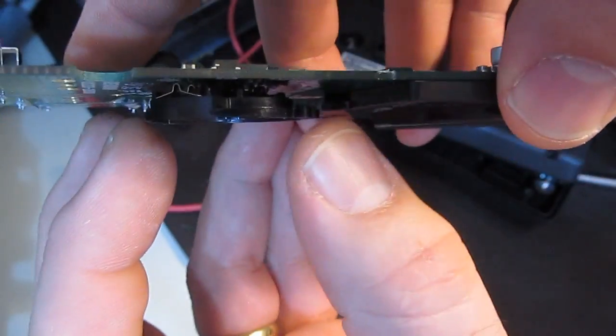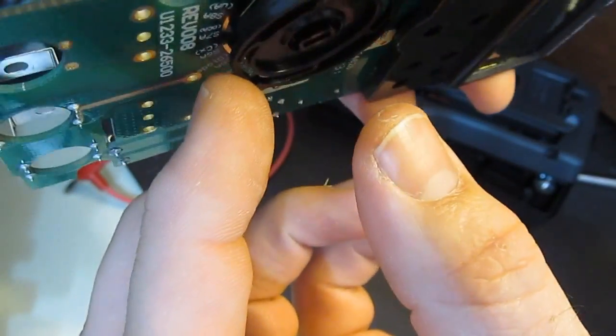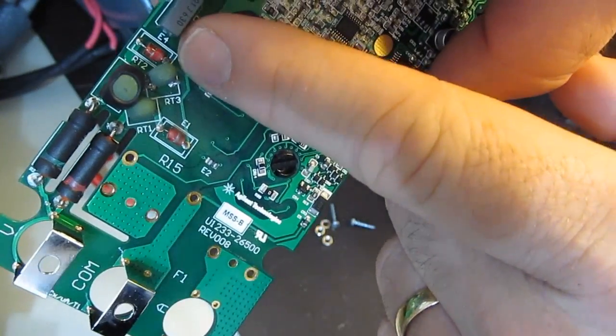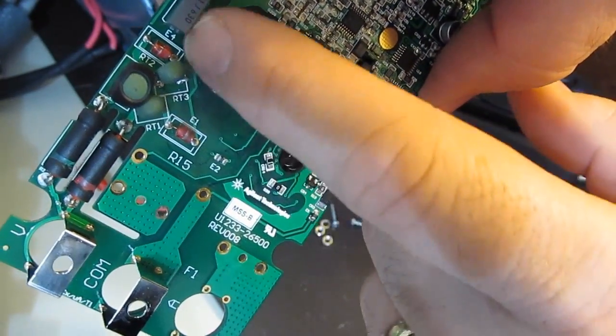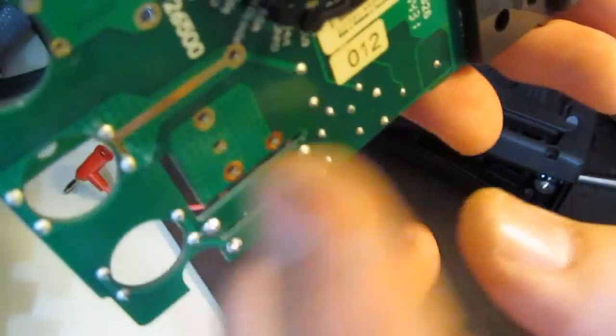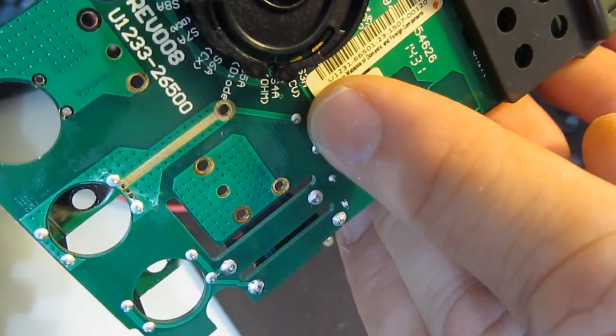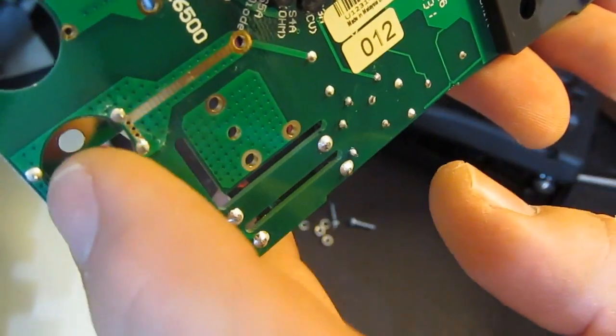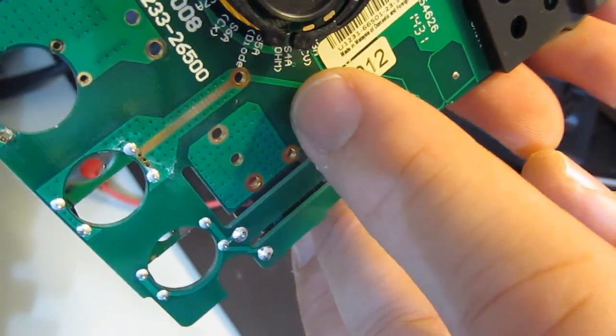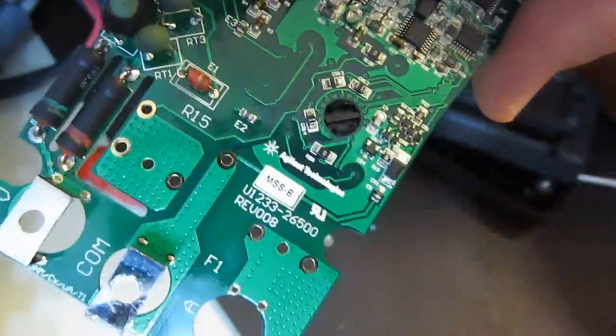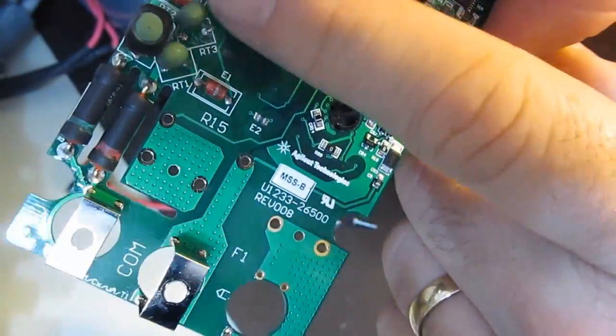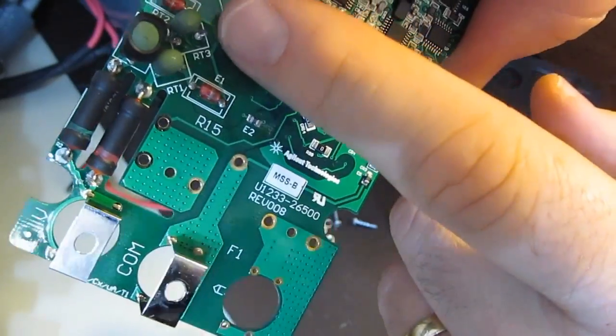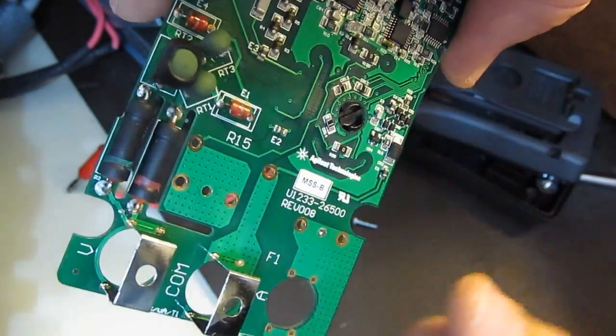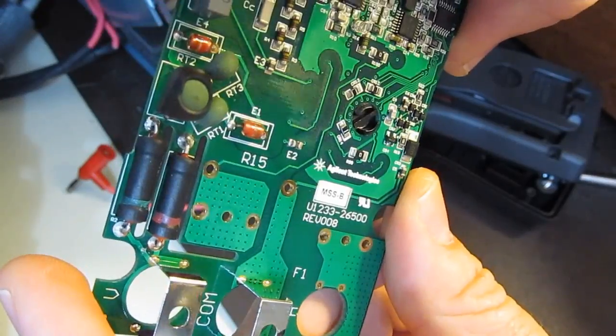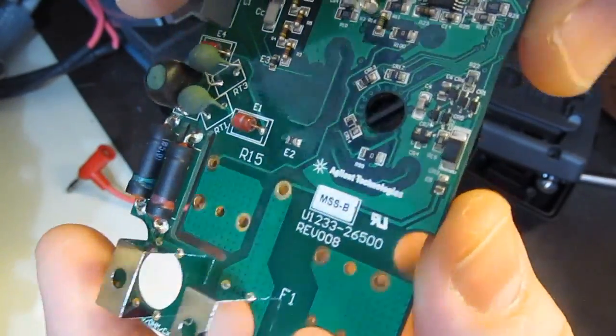I'm not real impressed with the switch. You can see this trace right here. That's the common trace that ties the two gas discharge tubes back to the ground reference. So that trace connects to here, so then goes down to our common return. There's going to be quite a bit of current that's going to flow through this, and I would not be surprised to see a trace that size actually get damaged. Yeah, I guess we'll have to go ahead and test it and we'll see.